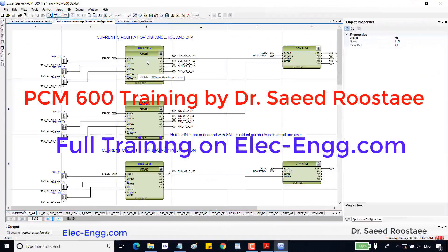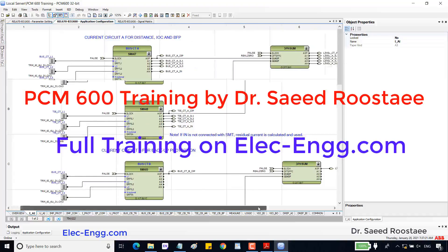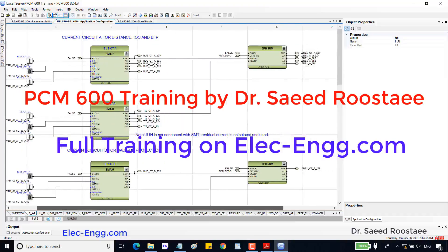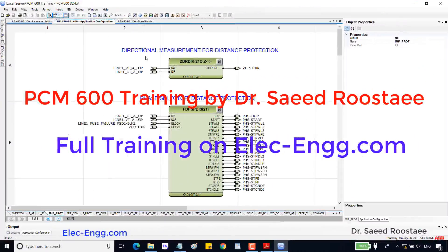A three-phase summation function block is used to add two current signals to be used by the protection functions. Single-phase signals can also be used for disturbance report function blocks. This block is for directional measurements for the distance function block.